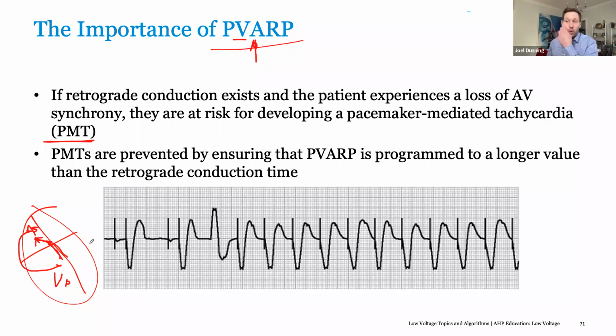rate. So with PVARP, what happens is when we have a ventricular event occur, the device effectively ignores anything that occurs in the atrium for a certain period of time. In this case here, for example, our PVARP is too short. We have a PVC. This causes a retrograde A, and you can actually see this P wave right here. The device sees it as an atrial event. It then V-paces, which causes a retrograde A, which the device sees as an atrial event, and it V-paces on and on forever.